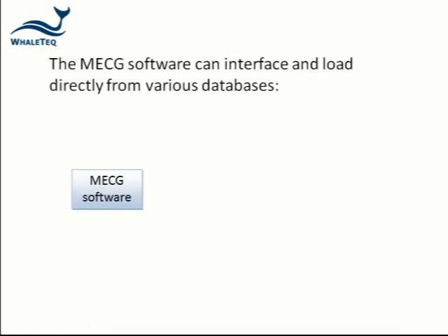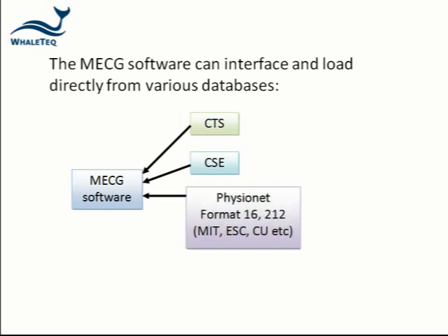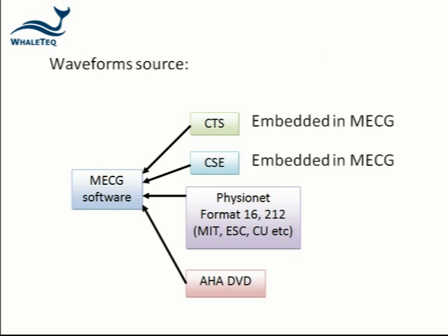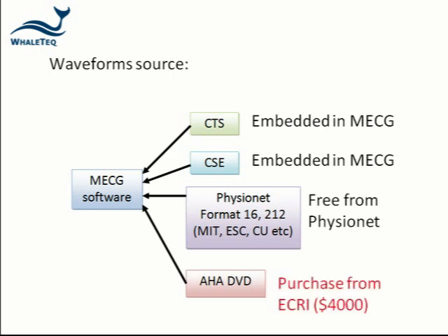The MECG software can interface with various databases. Each database has both waveforms and reference values. For CTS and CSE databases, the waveforms are embedded in the MECG software. For PhysioNet waveforms such as MIT, ESC and CU, these are available for free from the PhysioNet website, while the AHA database must be purchased directly from ECRI at around $4,000.